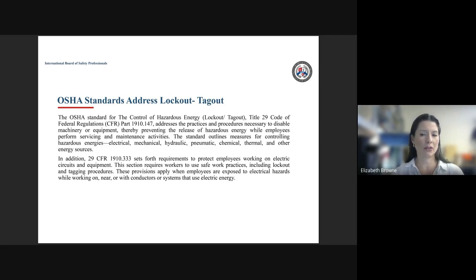It's important to point out that while a big focus for lockout tagout is on electrical hazards, there's all types of hazardous energy sources that equipment can have, and we must control all of those energy sources before an employee may work on that equipment. The section also requires workers to follow safe work practices, such as the lockout tagout procedure that has been prepared, as well as making sure that employees that are exposed to any electrical hazards that are working near the equipment are aware of that and are not in danger.